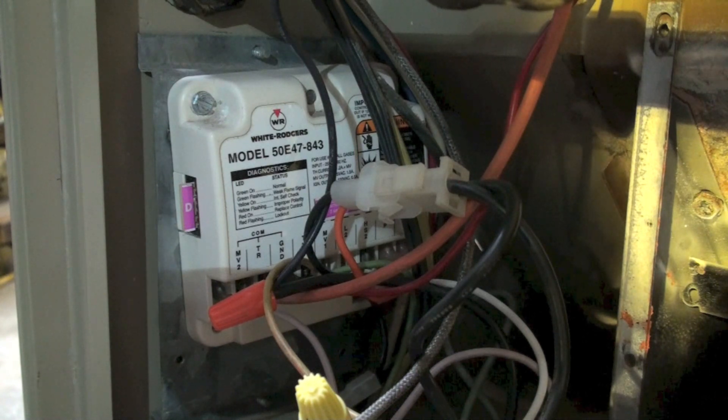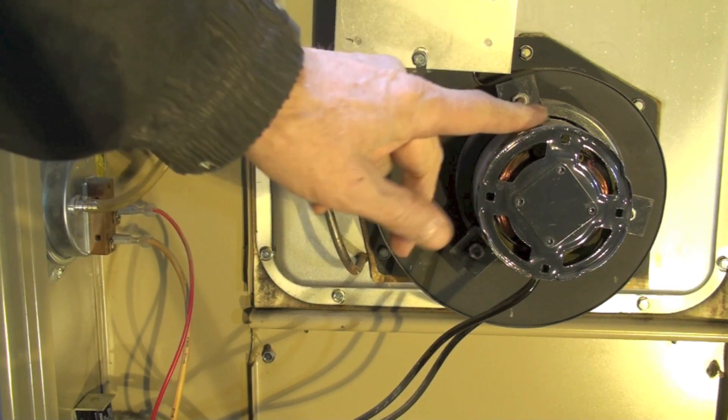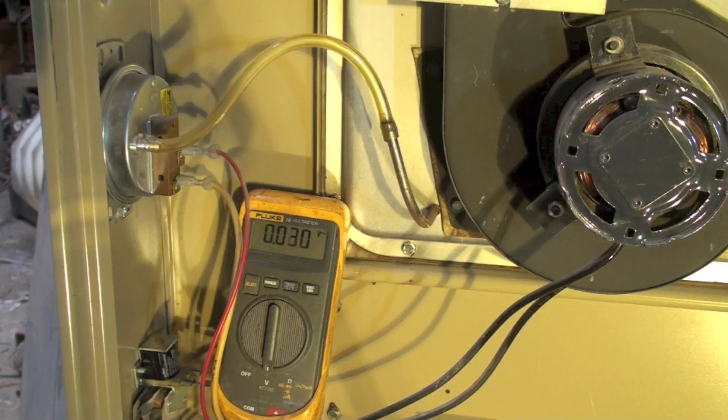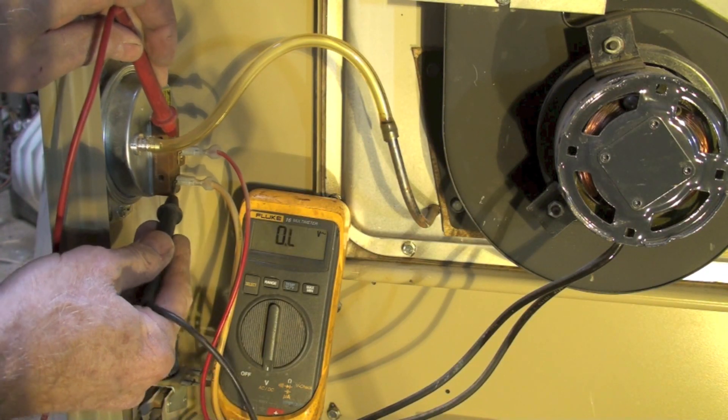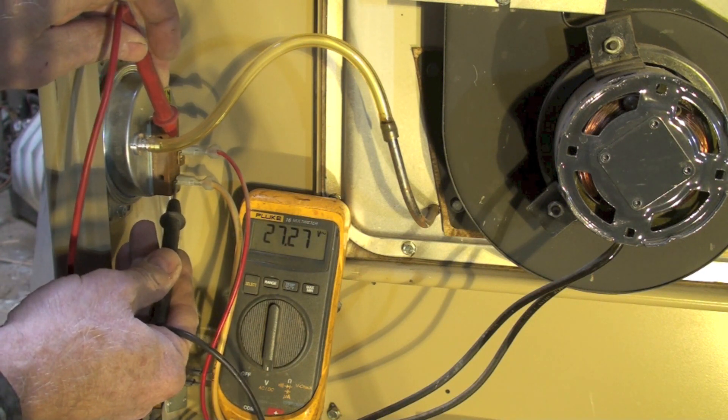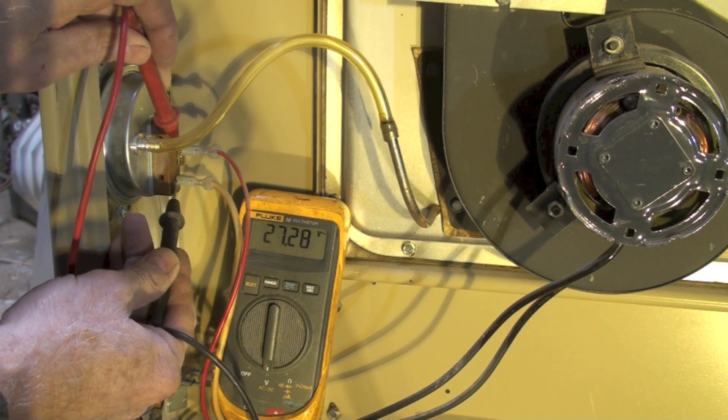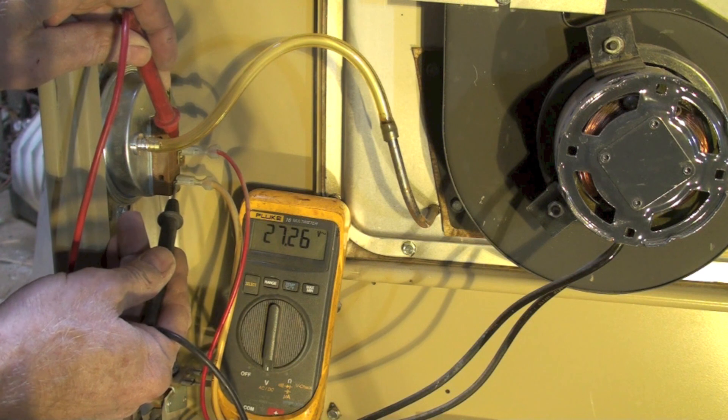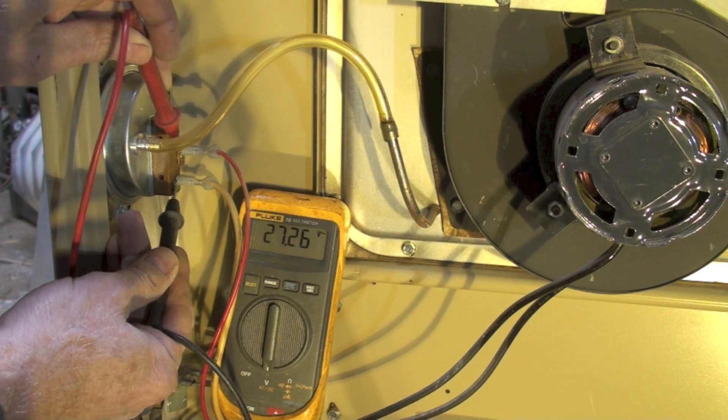Now here's one of the common reasons for this. My inducer's running, pressure switch is right here, but did my pressure switch make? Let's find out. I'm going to go across here. Now you can see I'm showing a voltage. That means the pressure switch hasn't closed, because if it had closed I would read zero across the pressure switch. So what's wrong?